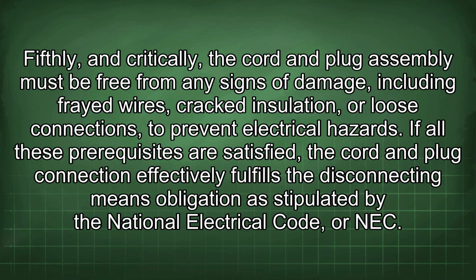Fifthly, and critically, the cord and plug assembly must be free from any signs of damage, including frayed wires, cracked insulation, or loose connections, to prevent electrical hazards. If all these prerequisites are satisfied, the cord and plug connection effectively fulfills the disconnecting means obligation as stipulated by the National Electrical Code, or NEC.